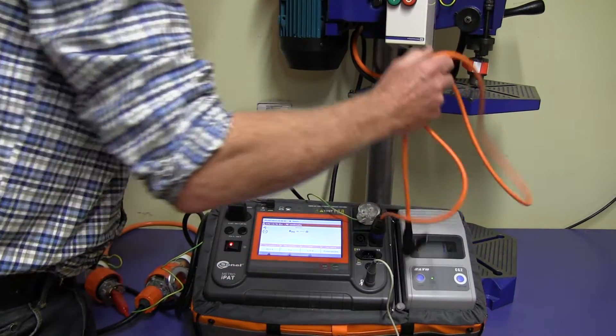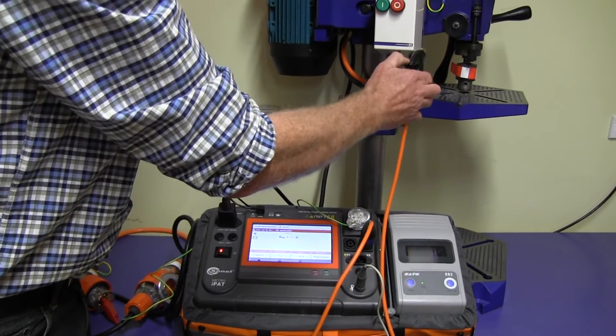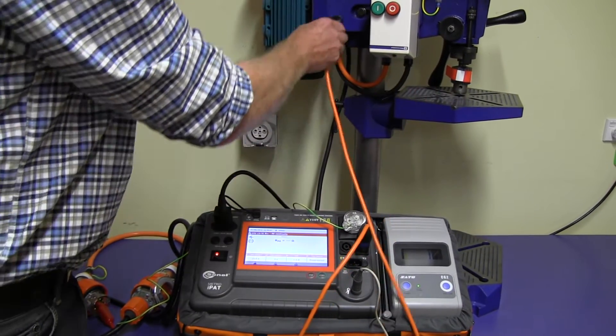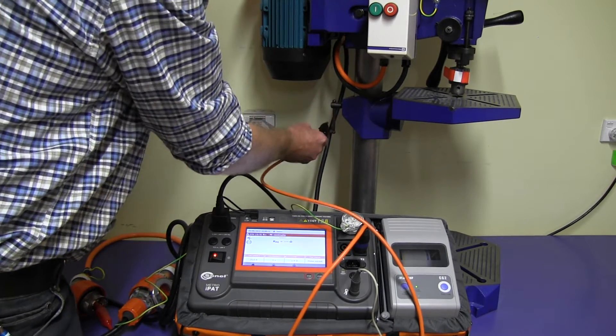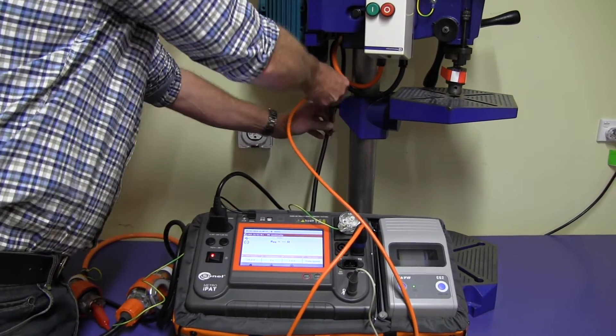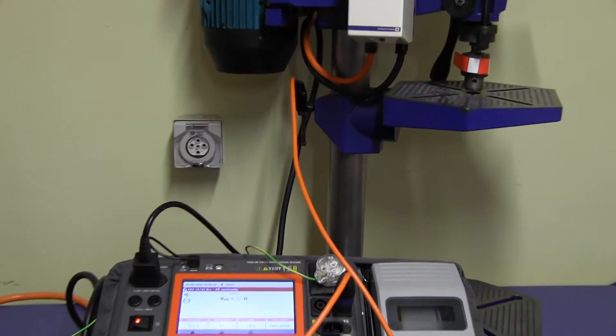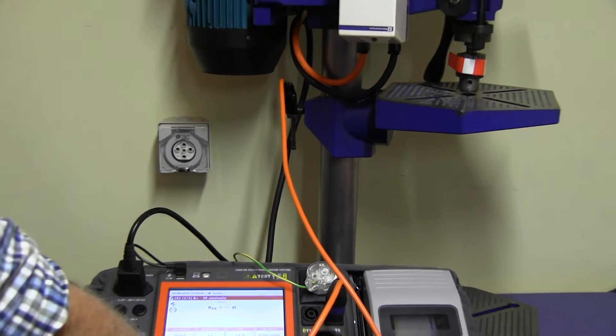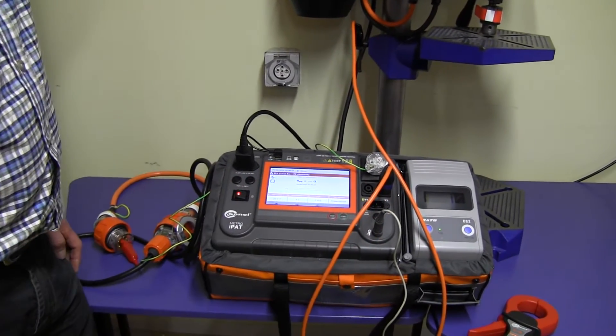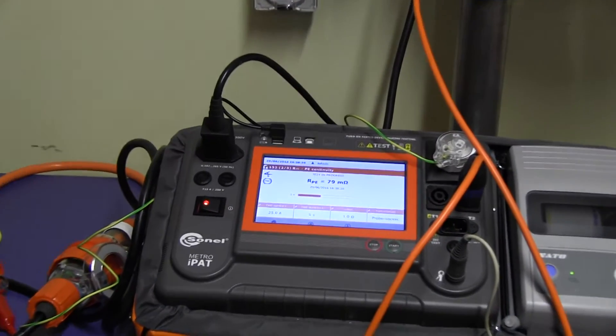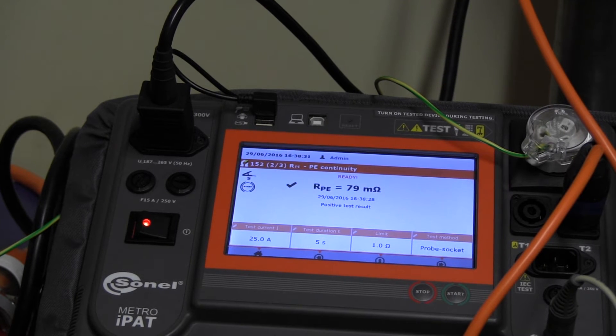The wander lead needs to go to a metal part of the three-phase appliance. We can clip it onto the drill press. Then we press start on the PAT tester. It's now measuring the earth resistance. It's coming back at 79 milliohms, which is really good.